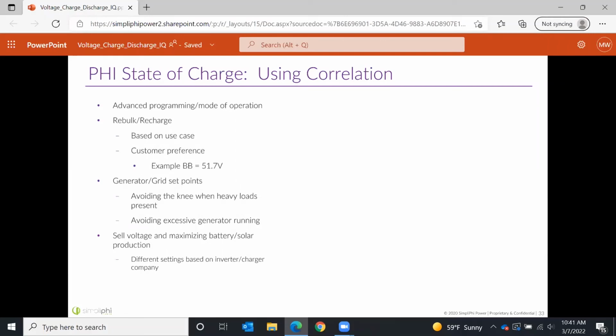Whereas for a customer who wants to keep the batteries full at 100% state of charge for backup during an outage, but still wants to sell at least a little power, I'd set this higher—maybe 53.2 or even 53.5. You definitely want it below the float voltage. For the best of both worlds, 52.8 is the general recommendation in most of our guides, but again, this is something you might want to mess around with.